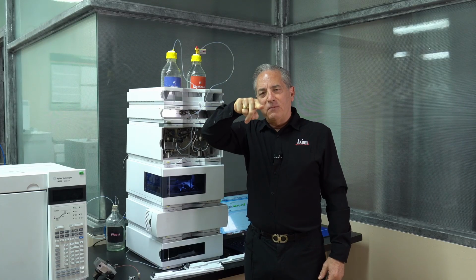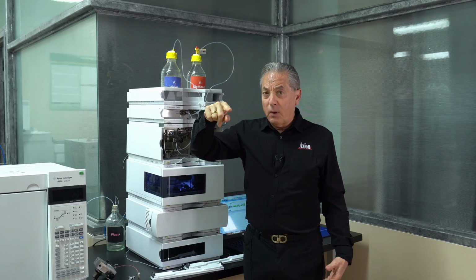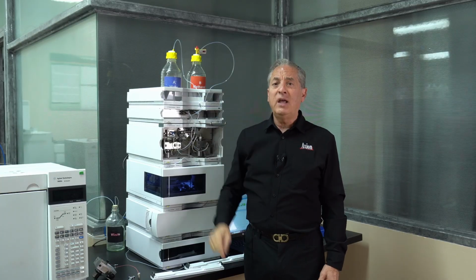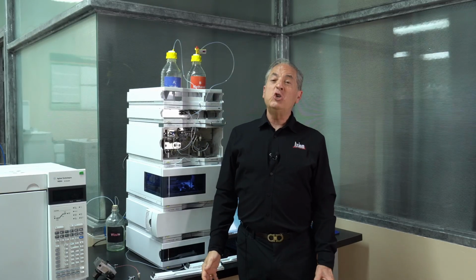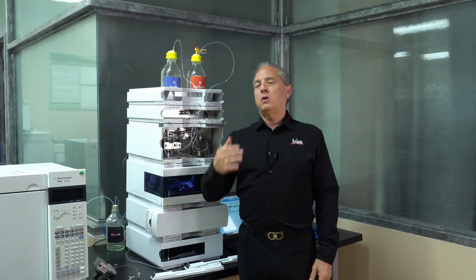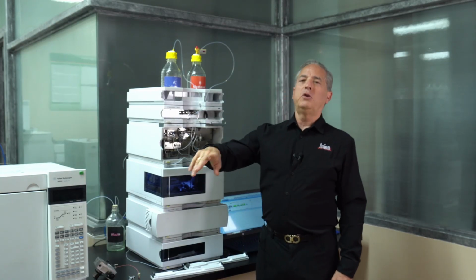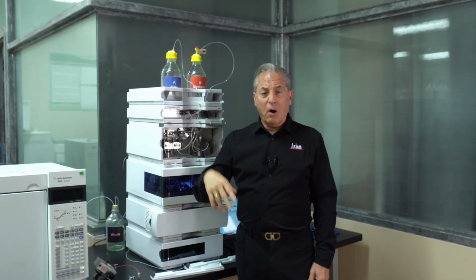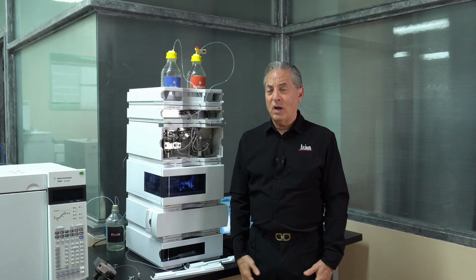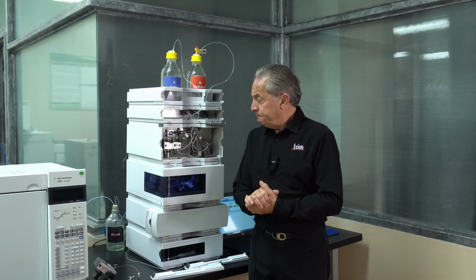In real life, there is some variation, and that variation is called the ripple, pressure ripple, or short-term pressure variation. By spec, it should be less than 2%. So if you're running 100 bar, then 2% would be plus or minus 2 bar. So you get the idea of how much you're allowed to have.